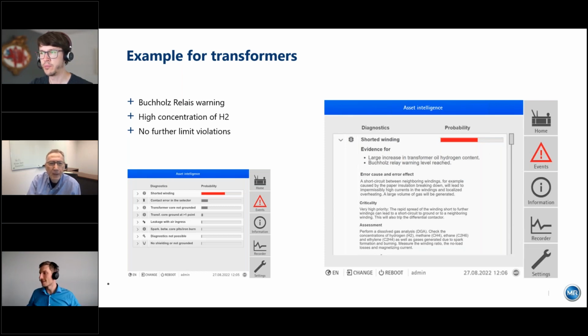To add to the previous points, Duval only gives you a fault classification, but to do this you have to be sure that some fault has actually occurred. So in reality, if you just look at DGA, you also have to combine some fault classification method like Duval with some other method, like C57.104, to determine if some fault has actually occurred. So even with DGA you already have to combine several methods to be sure that what you're doing is legit. The Asset Intelligence basically does this work for you and also includes non-DGA data points. So that would be my answer to this question.